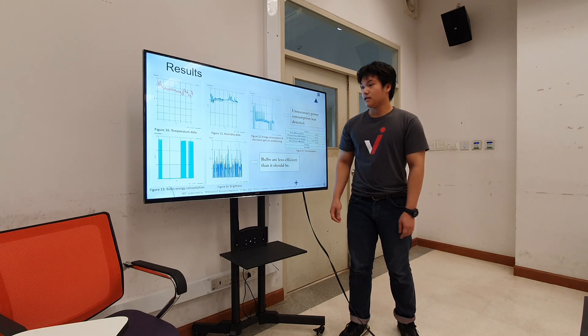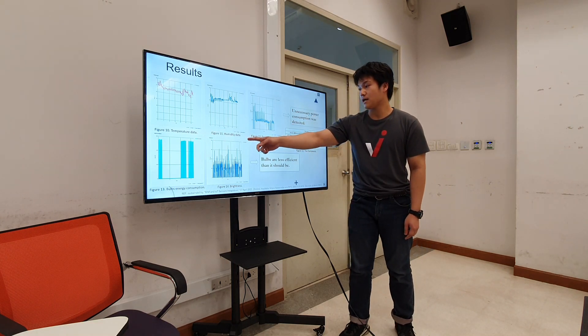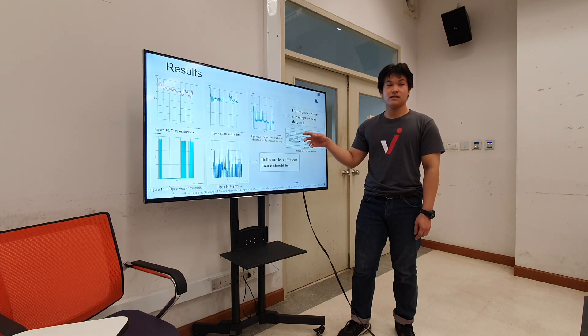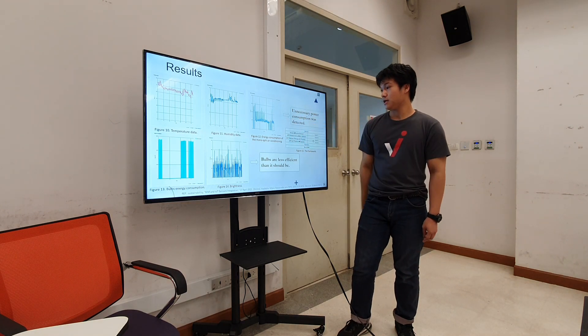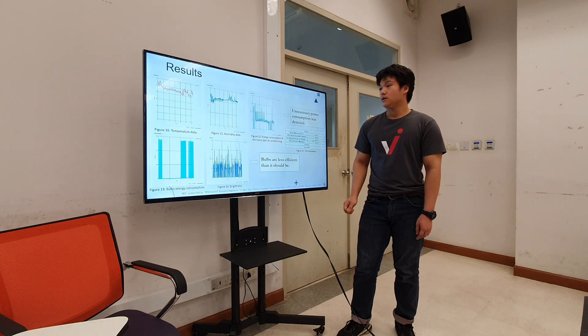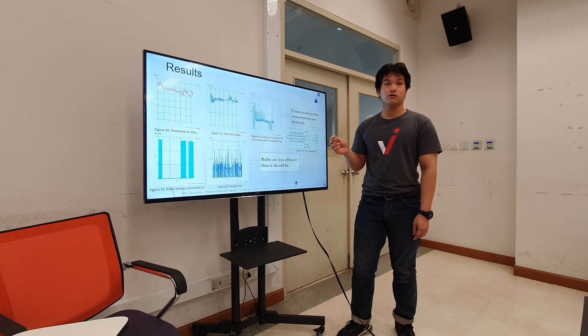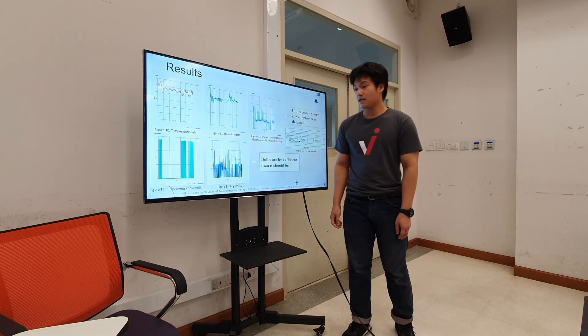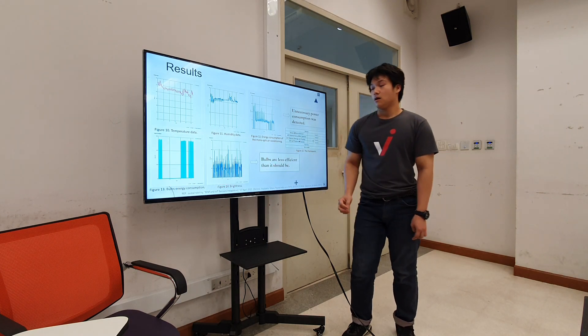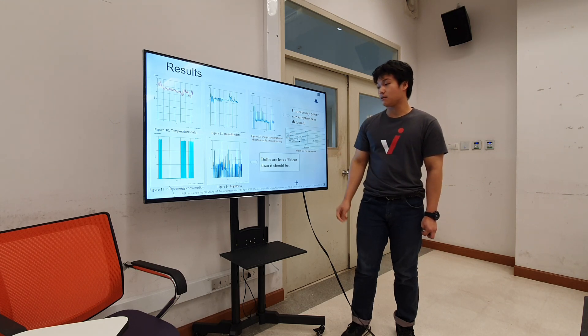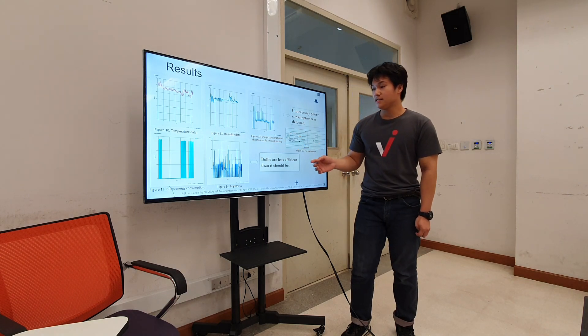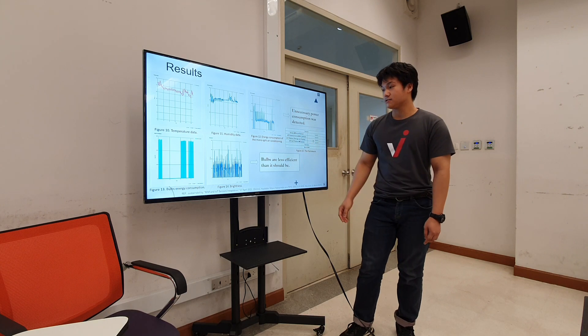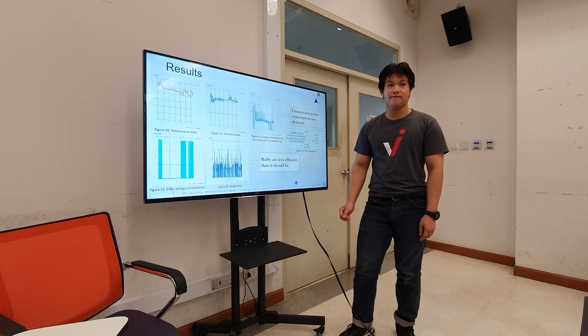Looking at the results: the graphical data for temperature, humidity, and energy consumption of the office air conditioning can be monitored continuously. Normally the air conditioner is turned on and off each day, but in the middle of the month it continues running as if it were a holiday. This shows that energy is being consumed even when no one is in the room, representing a significant waste of energy. Furthermore, looking at the energy consumption and illuminance data, even when the lights are turned on, the illuminance shows almost no difference and does not reach the standard of 500 lux, indicating that the lighting system is inefficient.